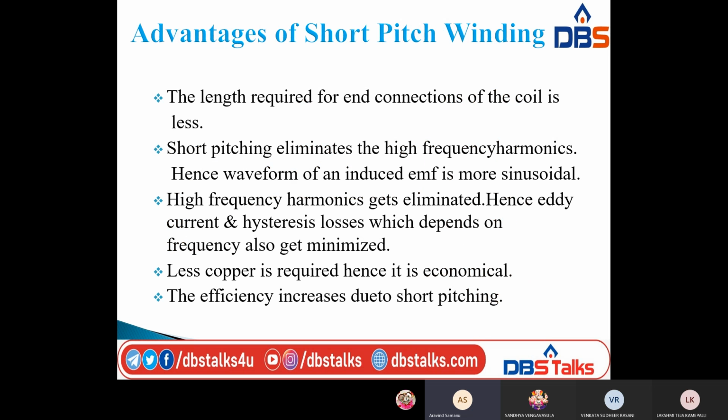Now the advantages of short pitch winding. First, the length required for end connections of the coil is less. Next, short pitching eliminates the high frequency harmonics. Hence, the waveform of the induced EMF is more sinusoidal. Why? Because short pitched winding eliminates the high frequency harmonics.